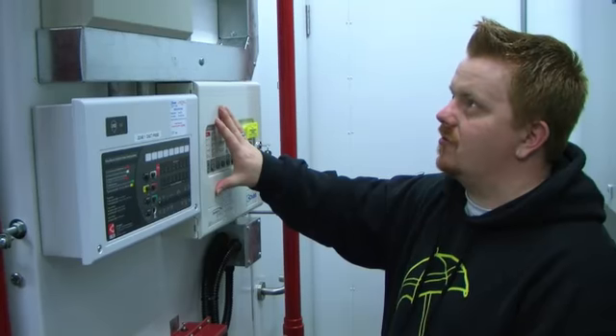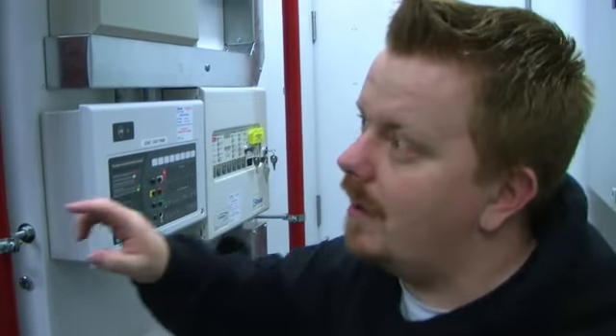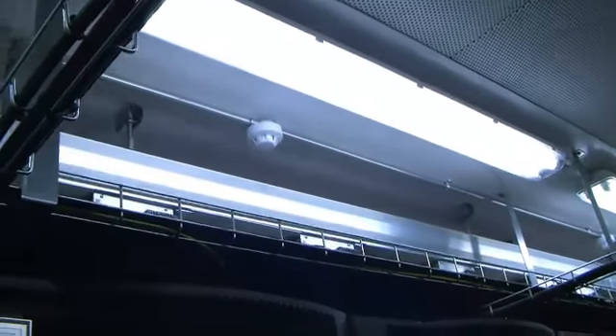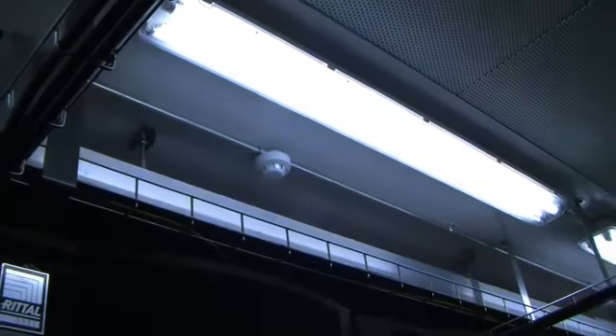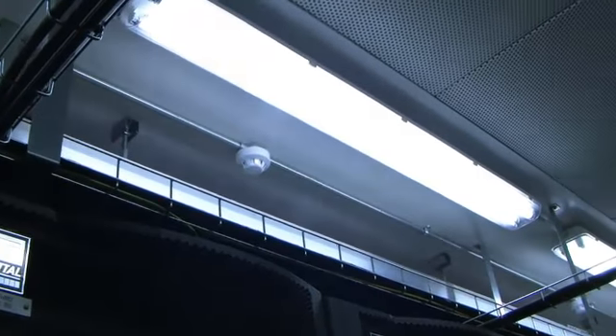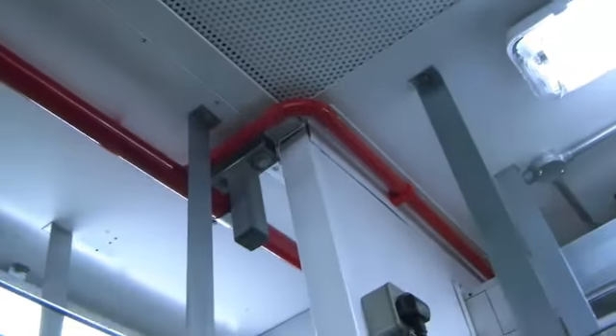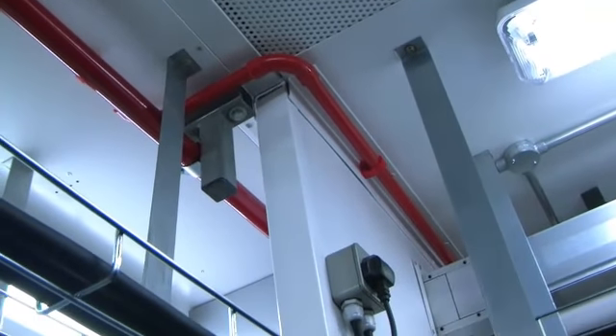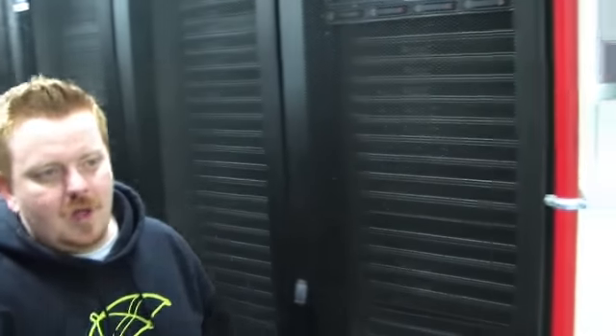Then we have our standard fire suppression system, which is actually pulling air samples into the smoke heads, which are these white heads. There's 3 in each cold aisle, and there's a couple dotted around different locations. They're smoke detectors. That's the second control loop, and the third control loop is the slightly smaller red pipe, the plastic one that runs back into the hot aisle, and that's a VESDA. It's a very early smoke detection system, but it samples so many particles per second, and if it detects any kind of particles in the air within the pod, it's able to tell us. And the system's in auto manual mode, which means that someone actually has to press a button to crank out the FM200 for safety, really.